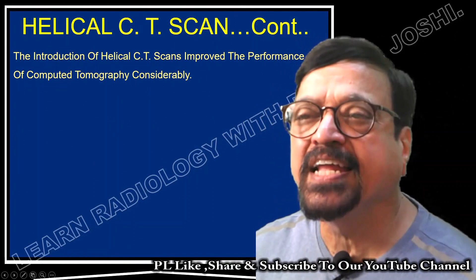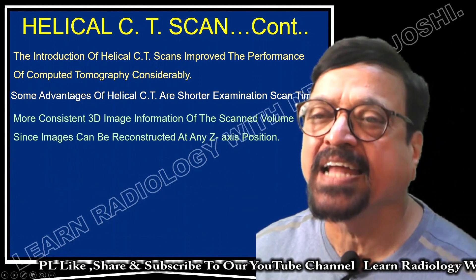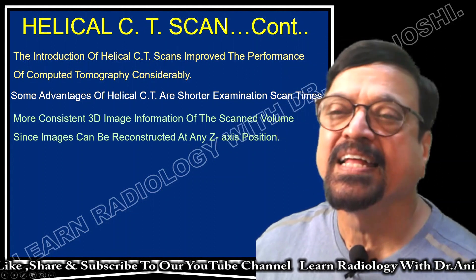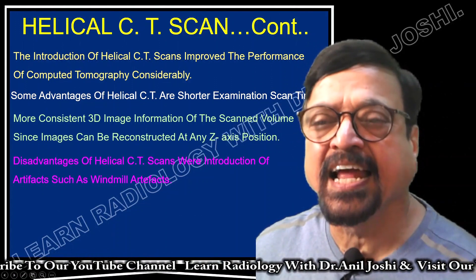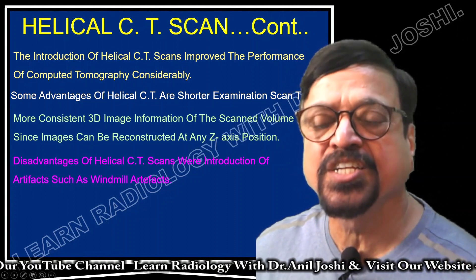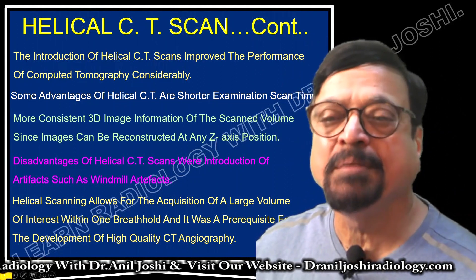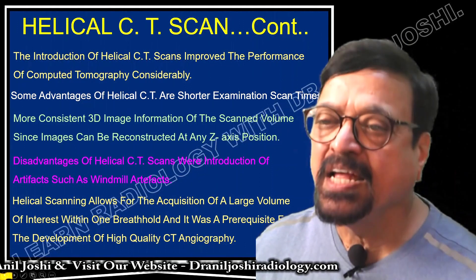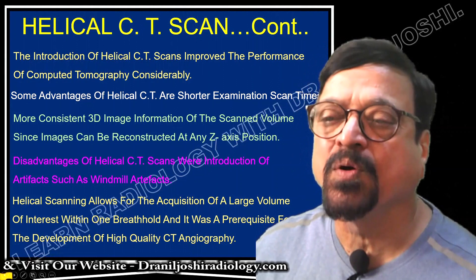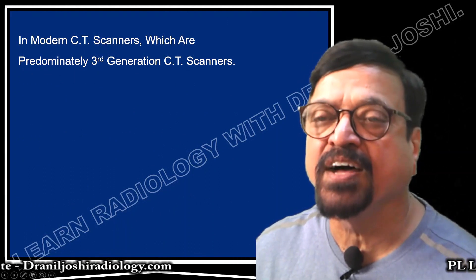The introduction of helical CT scan considerably improved the performance of computed tomography. Advantages include shorter examination scan time and more consistent CT images since images can be reconstructed at any axis — x, y, z — making coronal, axial, and even angular reconstructions possible. One drawback of helical CT scans is the introduction of artifacts such as windmill artifacts — a cost paid for the gains. Helical scanning allows acquisition of a large volume within one breath hold and was a prerequisite for high quality CT angiography, where fast scanning is needed as contrast dye moves quickly through arteries.